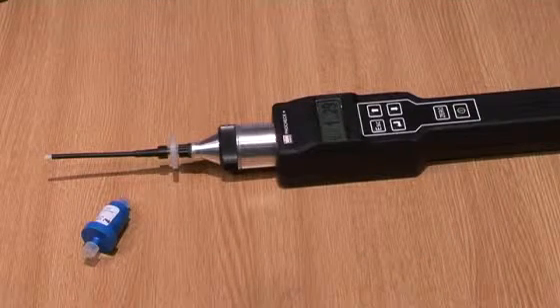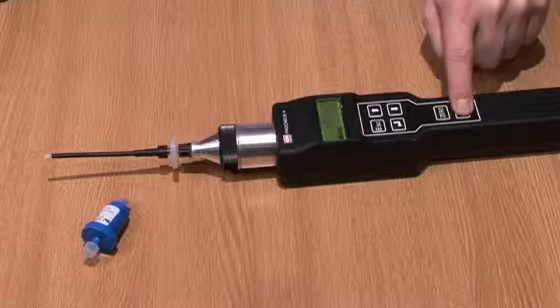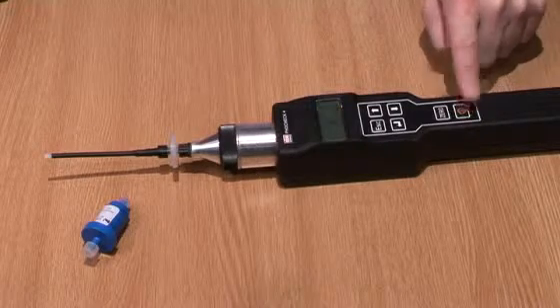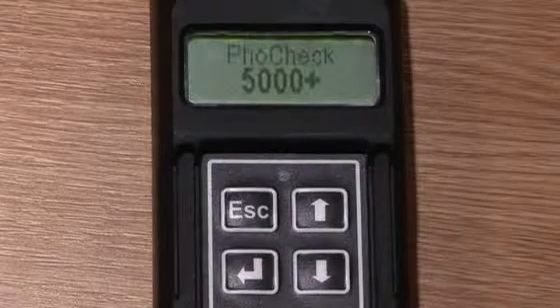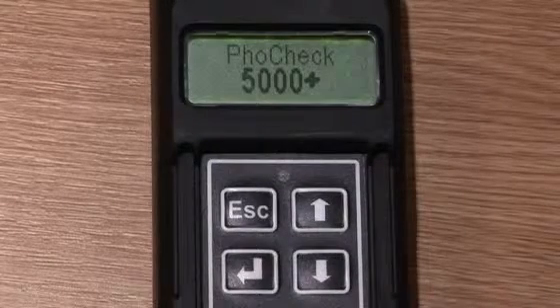To perform a function test on the unit, switch off the instrument to store the new calibration data in secure memory. On startup, the instrument will read the calibration data as stored in memory.